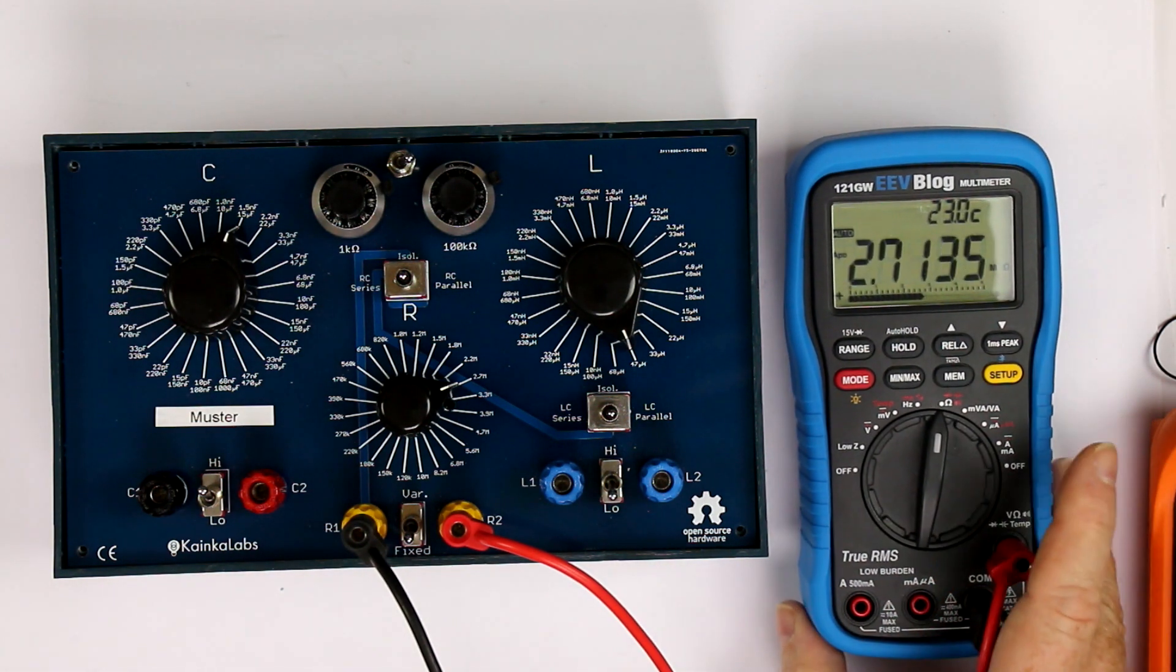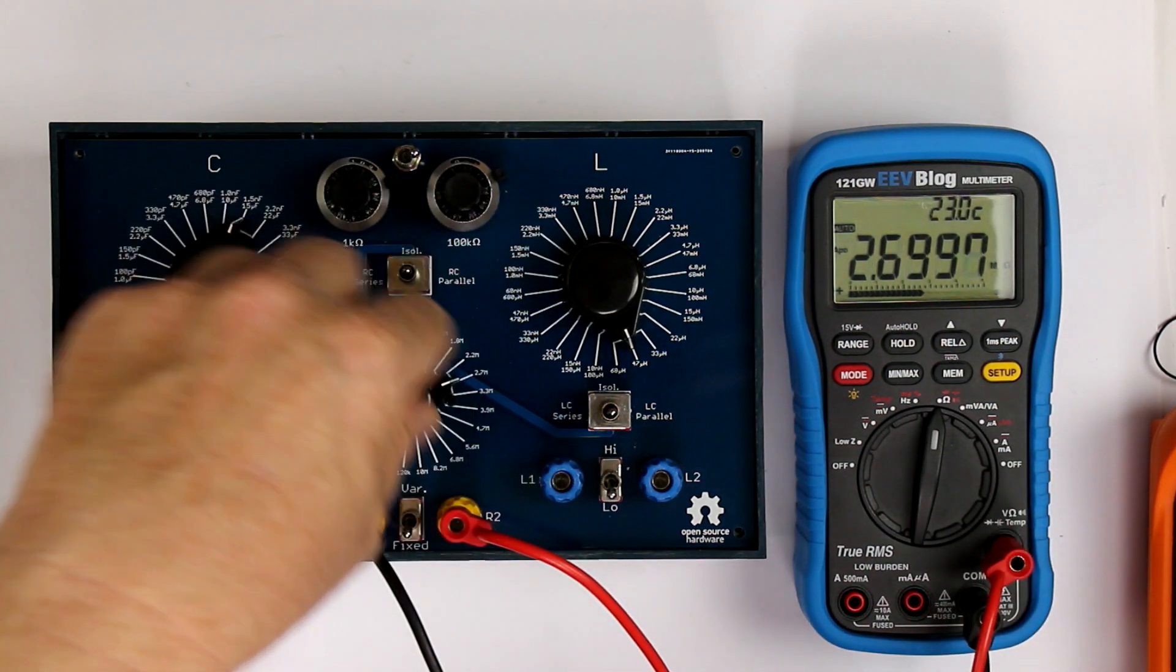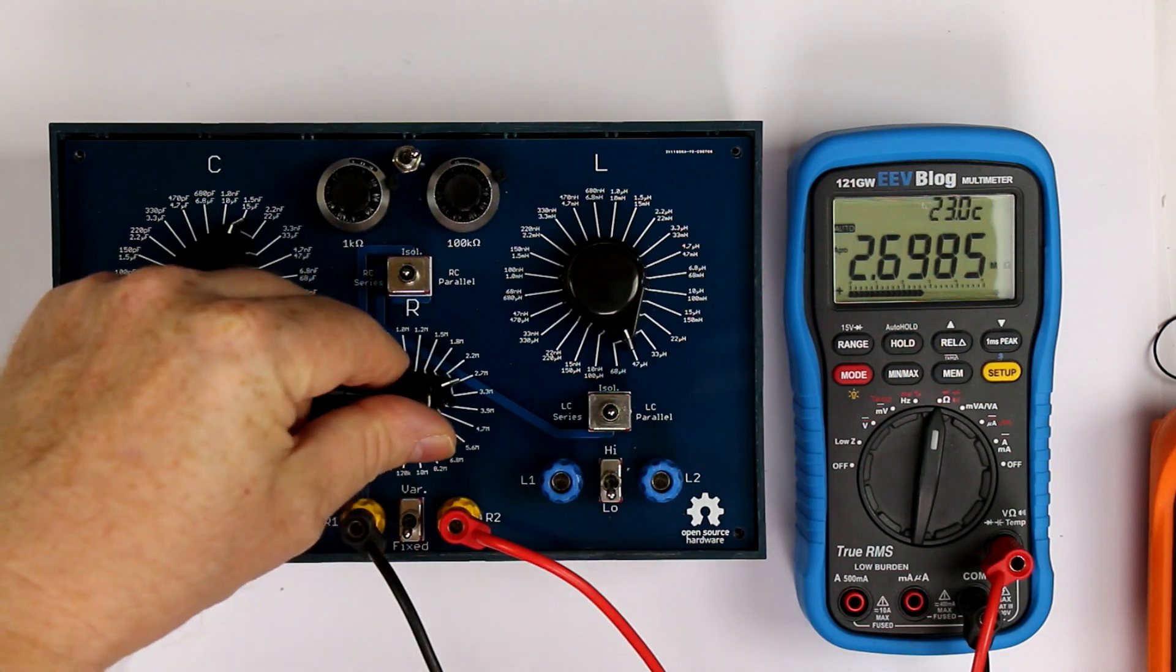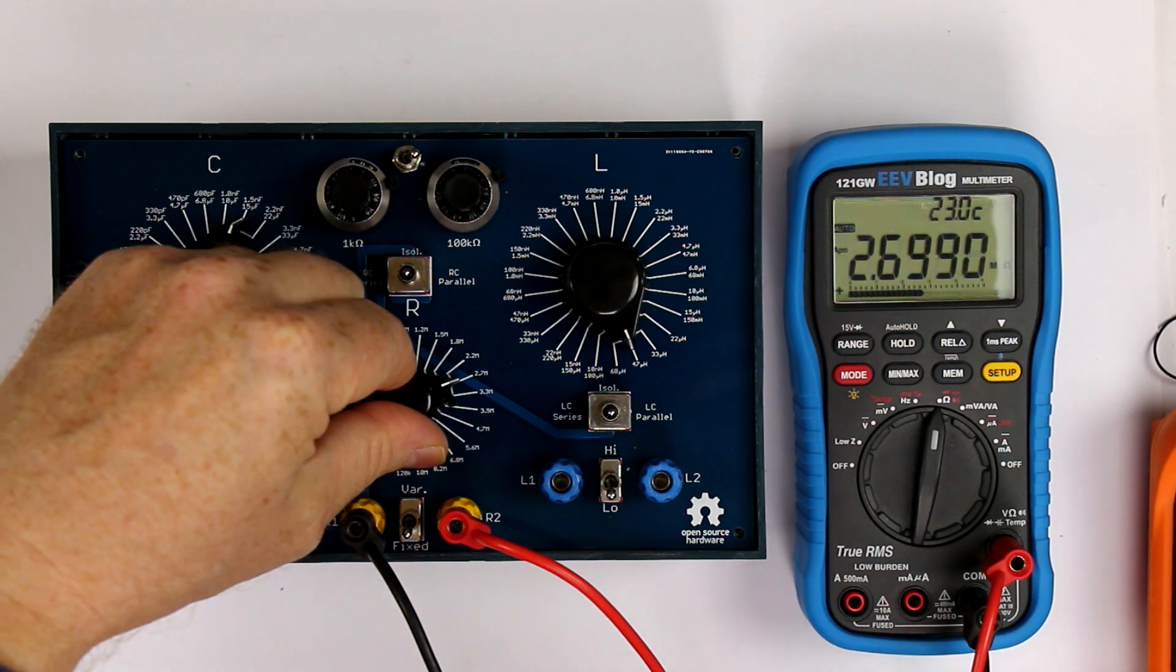Now let's exchange this with the 121 GW. Firmware is 2.0 for those of you who want to know, and at 2.0 I just have to check if the switches for the filters are in the middle position so that resistance is really isolated from capacitance and inductance.